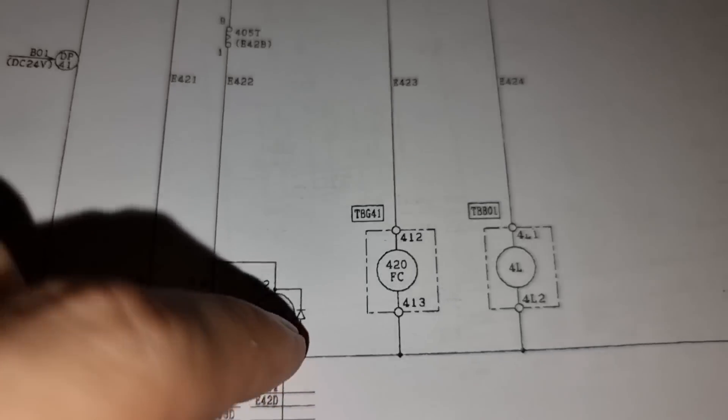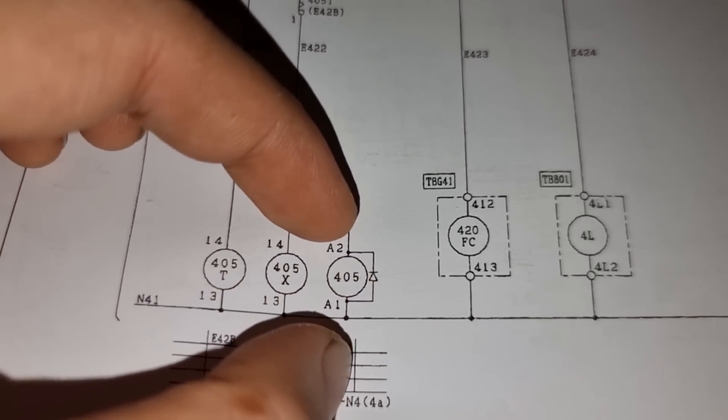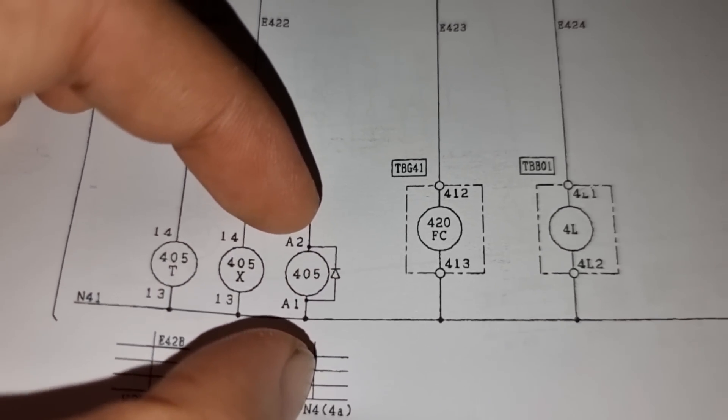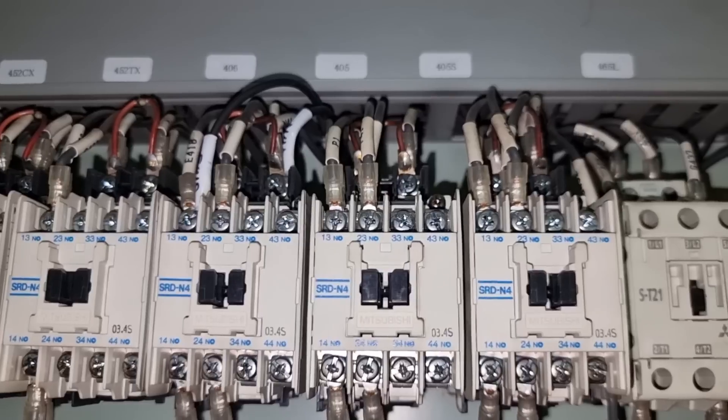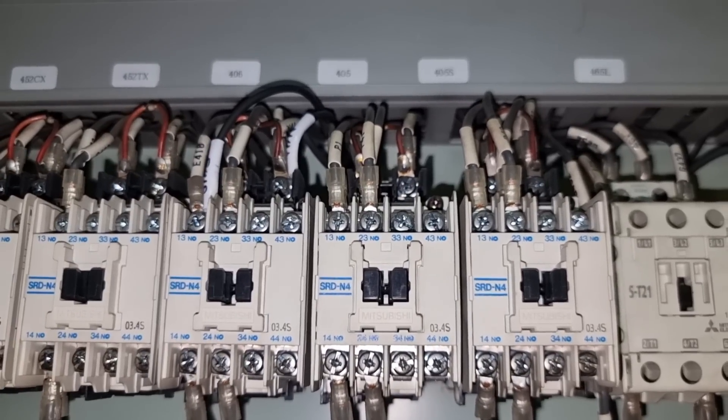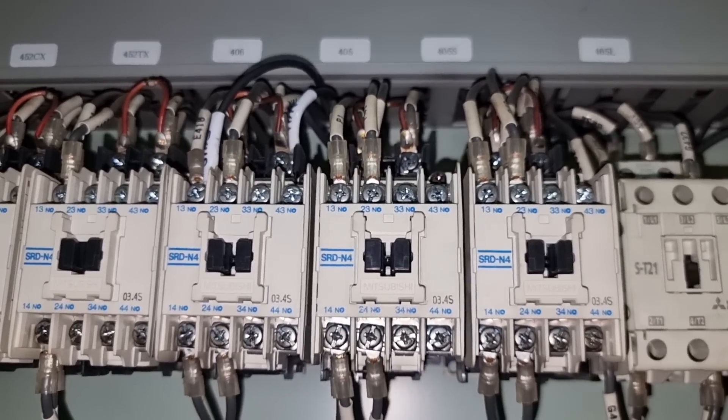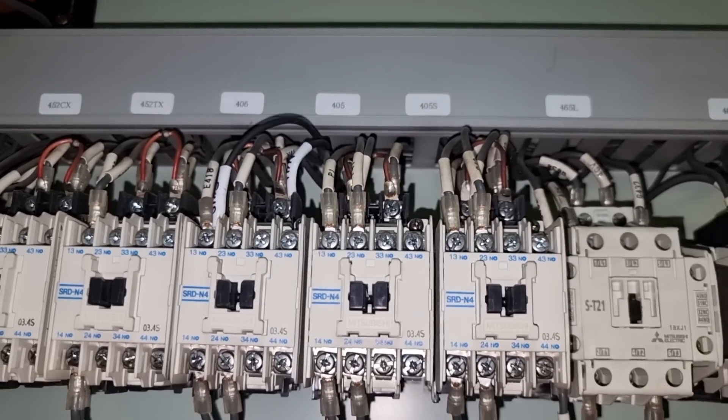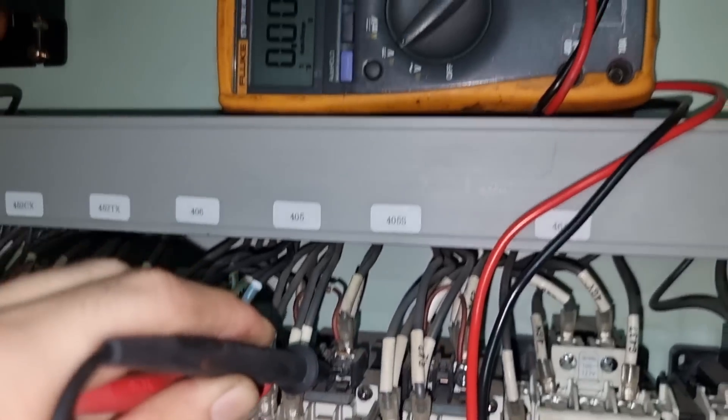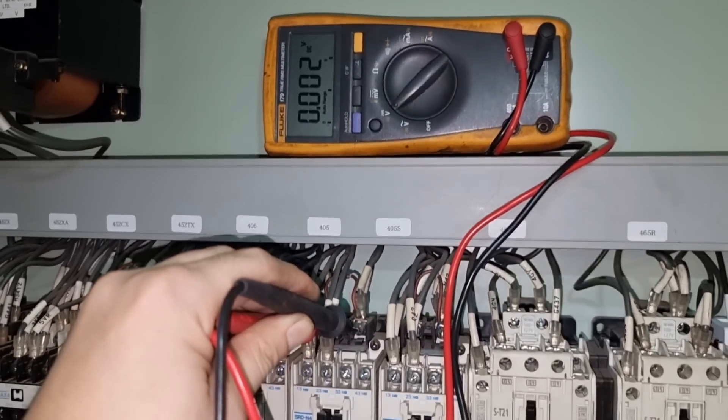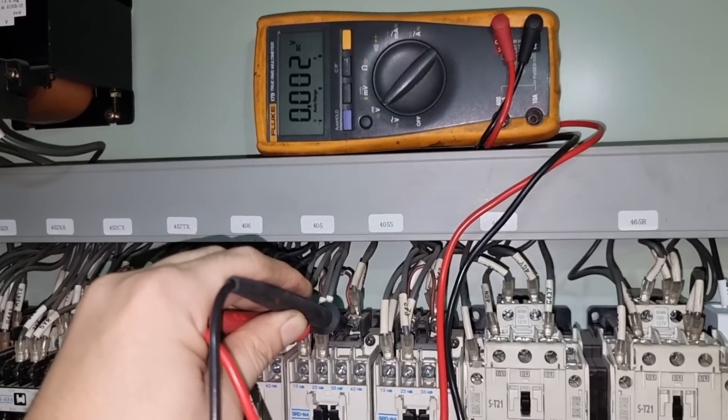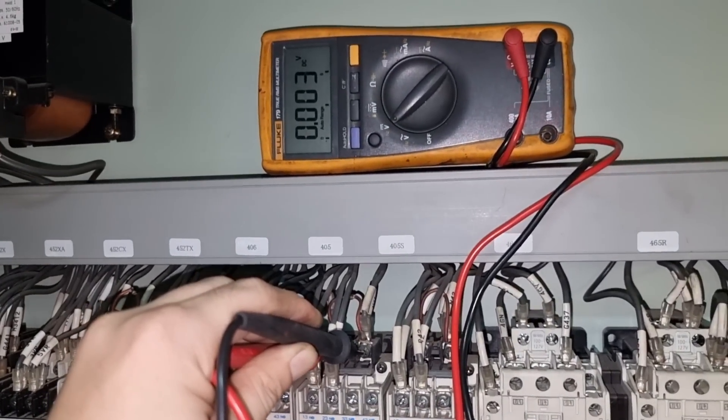To check, we also need to measure the voltage on A1 and A2. So this is the 405 contactor. Again, I will ask the engineer to activate the stop command onto the server and see if we are having 24 volts onto the A1 and A2 of this contactor.